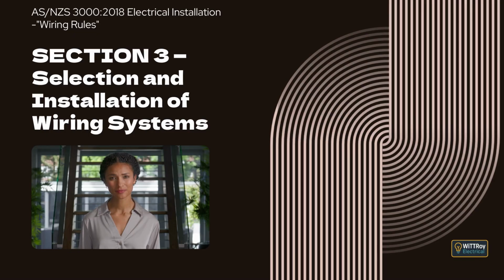Clause 3.10.3 Installation of wiring enclosures. This clause explains that wiring enclosures must be installed using safe and sound practice and must provide adequate protection in accordance with the requirements of Clause 3.3 and the following clauses. Clause 3.10.3.1 General. This clause explains that wiring enclosures must be installed so they do not obstruct natural water drainage on roofing materials and do not promote the buildup of debris. This may be achieved by installing the enclosure across the roofing profile or by installing it within valleys or trays using suitable supports such as standoff brackets.